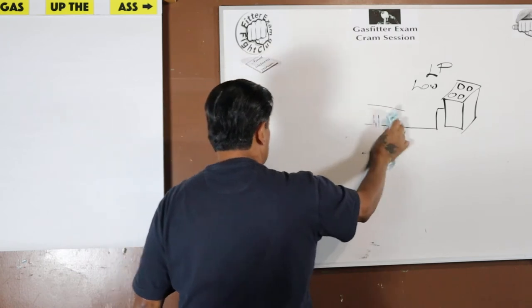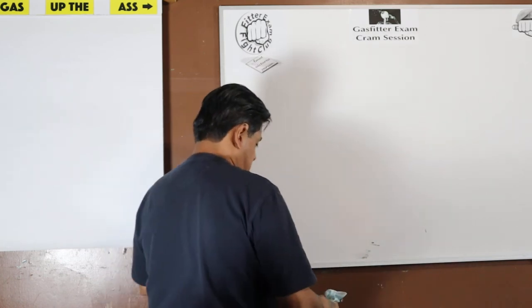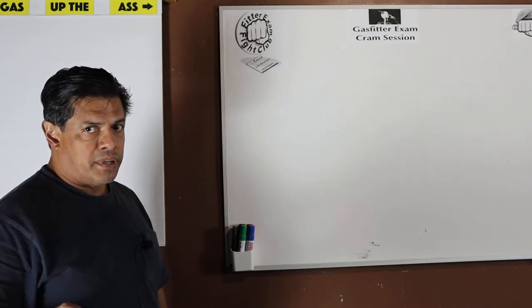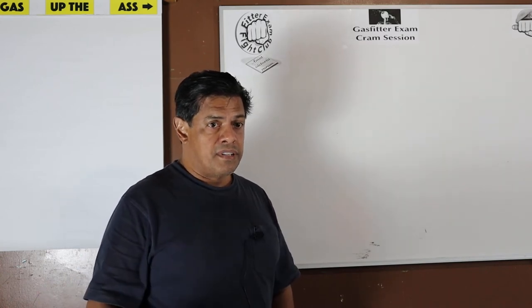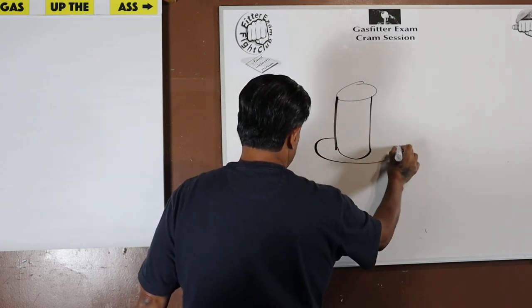And we have a water heater installed in a location, a space, whatever you want to say, where you know what happens to water heaters, right? You start getting close to the 10, let's say the 5 year mark, there's a chance you walk down to the basement and the basement's flooded. Why? The water heater rusted out in the middle of the night and it's all over the place, so that's why your shower was so cold that morning, okay? Your water heater's done for. In an unfinished basement, you'd be fine. You've got a mess, but okay. If it's anywhere else where that kind of water is going to cause a major disruption, damage to property, etc., your water heater is going to sit in a drain pan, okay?